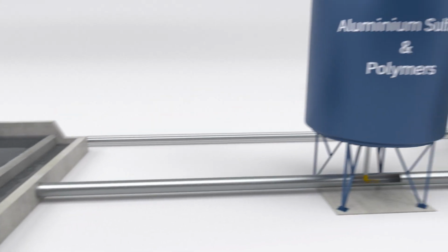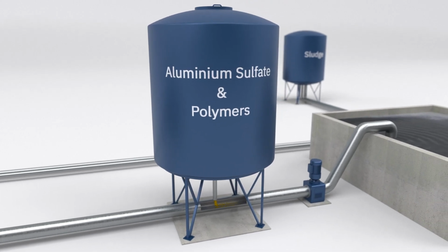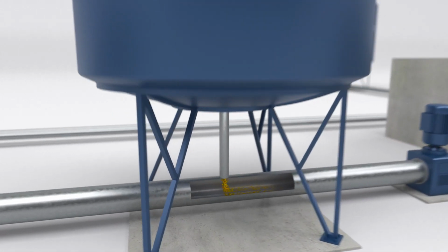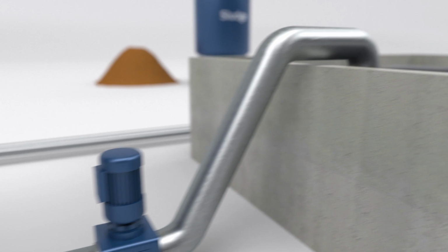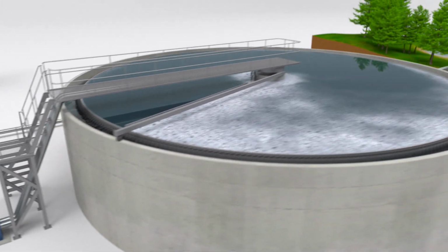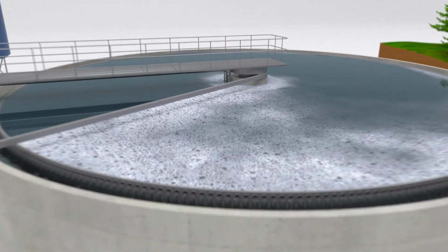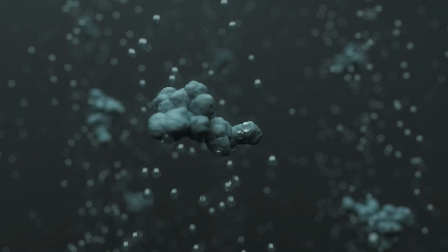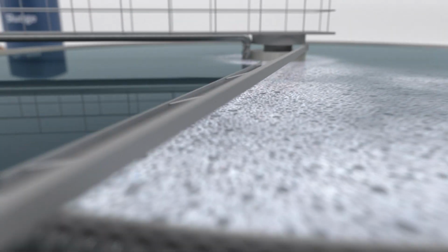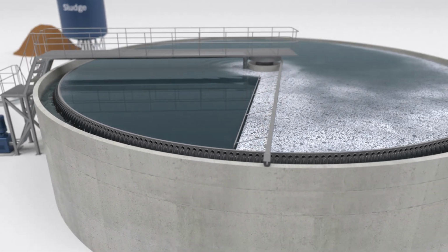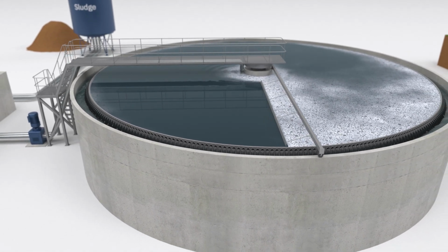If the biologically treated water needs extra cleaning, this can be achieved by adding flocculation chemicals in the flotation step. The chemicals create flocks with the remaining sludge particles and organic compounds. In the flotation basin, tiny air bubbles attach themselves to the flocks and bring them to the surface, forming a floating foam. The foam is removed and the water has now been thoroughly cleansed from particles and carbon compounds.